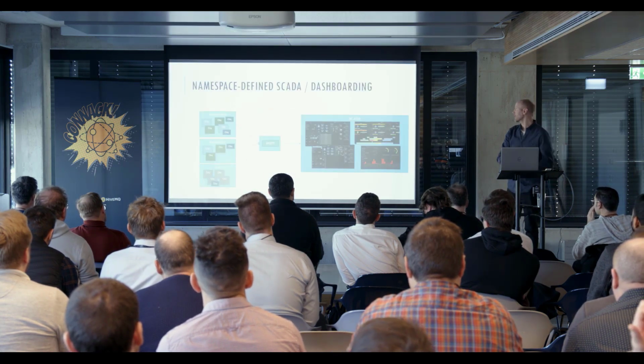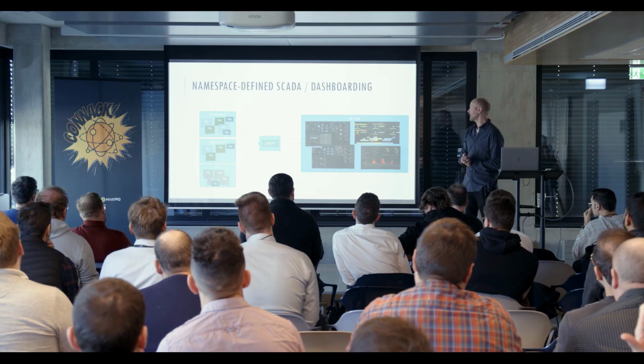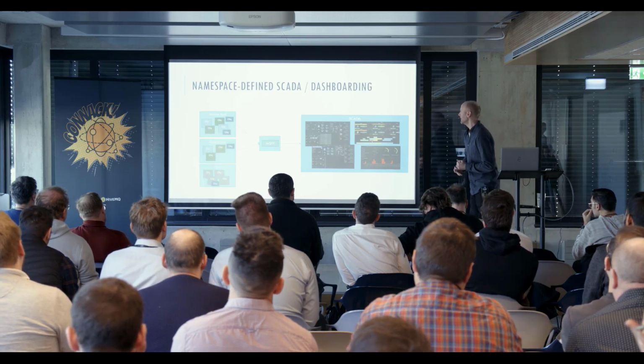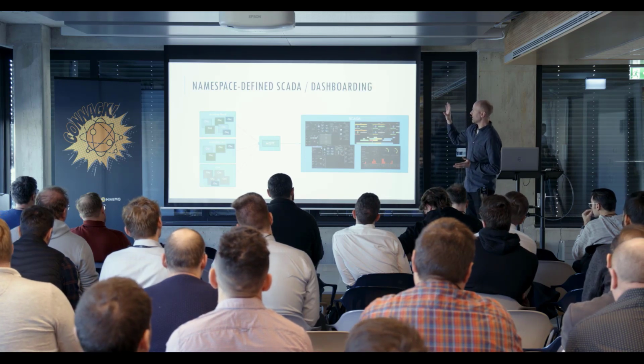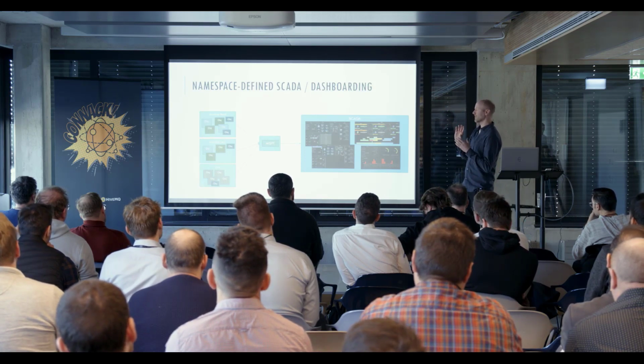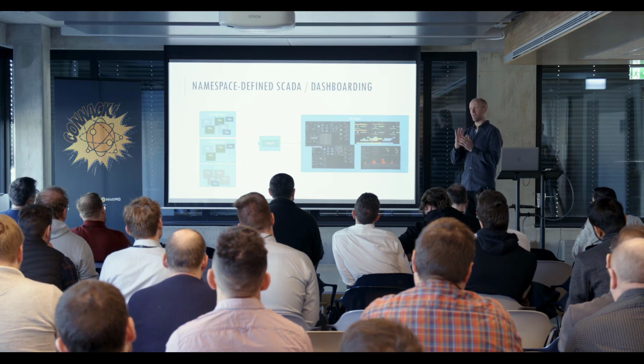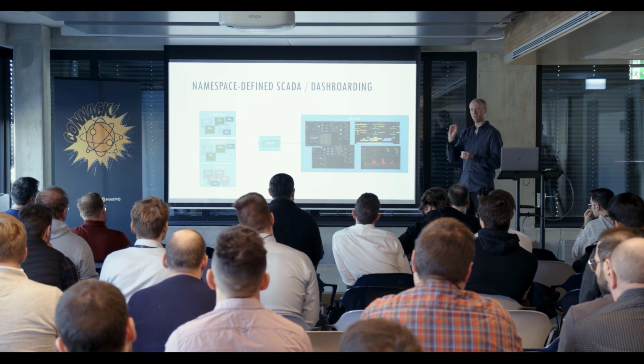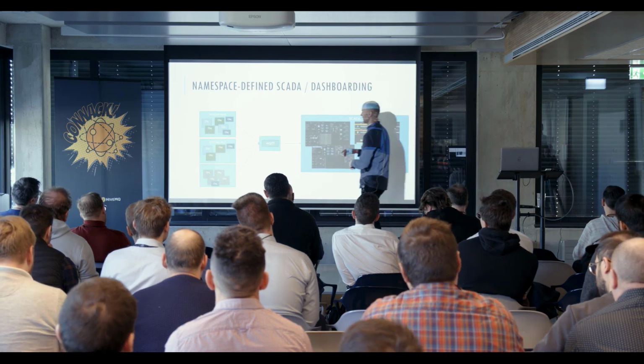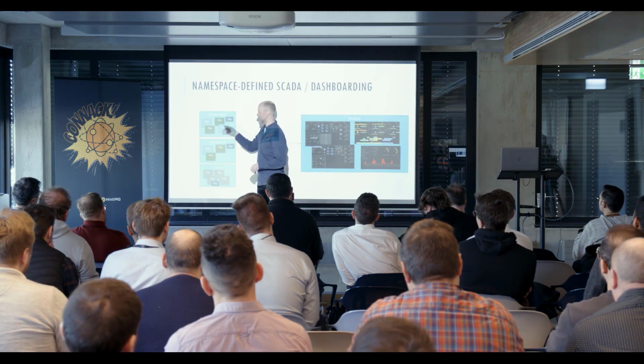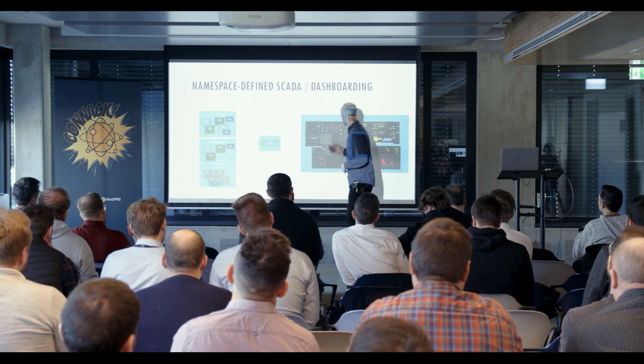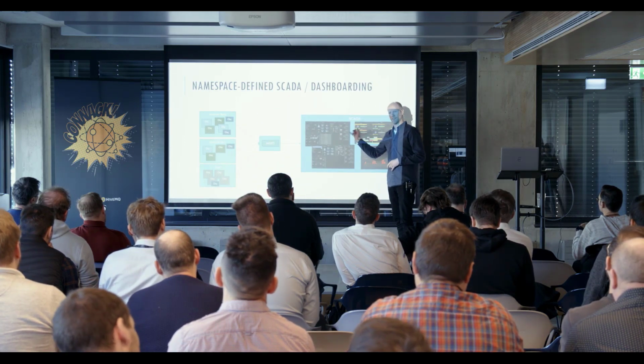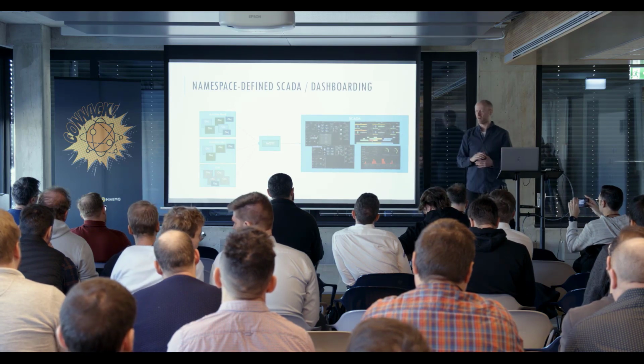The other thing we can do is make a namespace-defined SCADA/dashboarding. We have many machines, not necessarily the same revision of software, features and functionality. Sparkplug defines these objects and what they contain, and our SCADA system automatically reflects this - we don't have to configure that part. The same is true if we add machines to the network - they just appear in the SCADA system because of this auto-discovery.